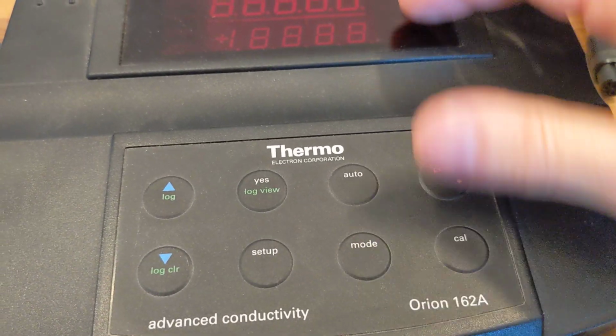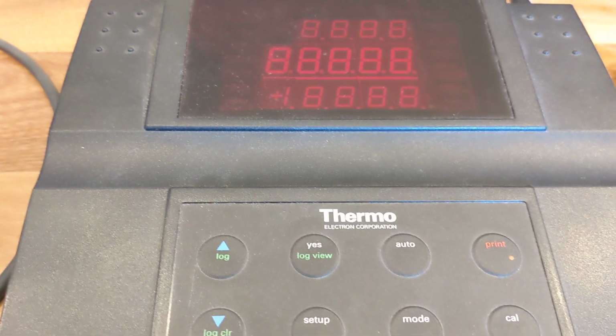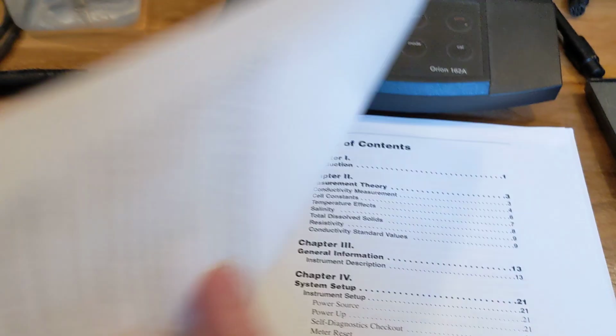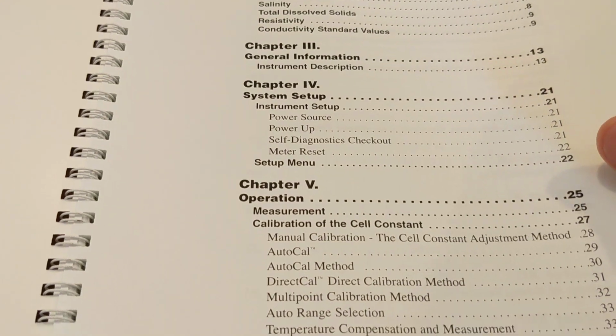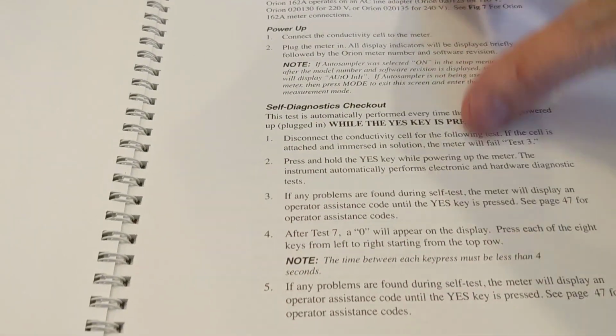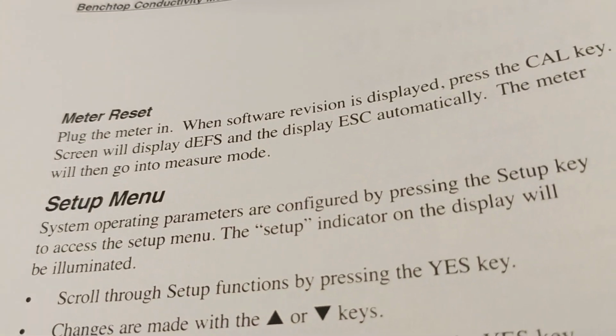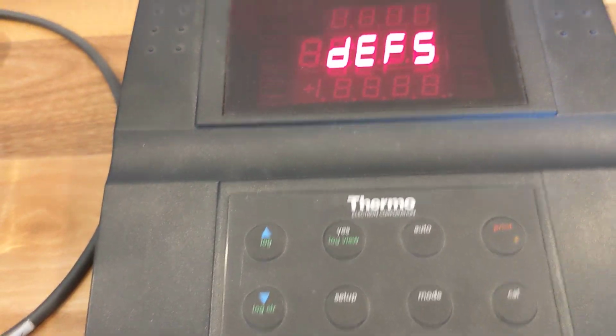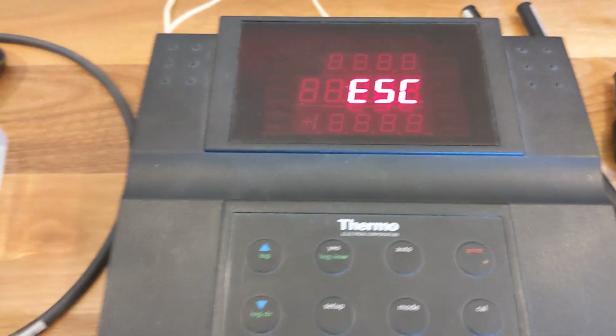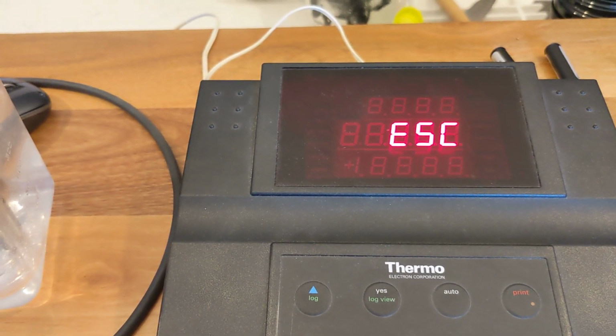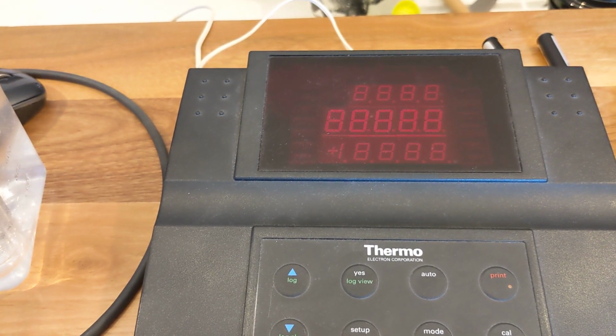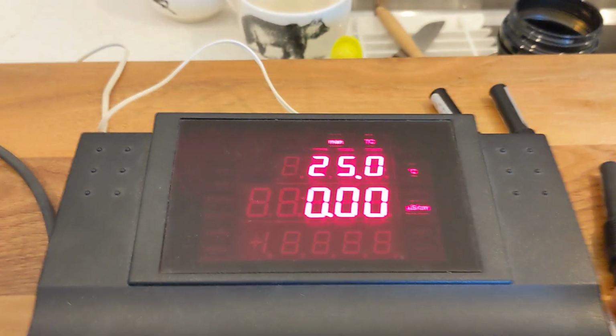All right, well, as I said, let's try factory defaulting it. I happen to know that if you press the, I think it's the yes, is it the cal button or the yes button? See, here's where the manual comes in handy. Let's take a look. Meter reset is page 22. So we have two things we can do. One is we plug it in and press the cal key while the software revision is displayed. So there's the software revision. There's cal defs for defaults. It'll give us an ESC automatically and then go into measure mode. All right, there's measure mode.